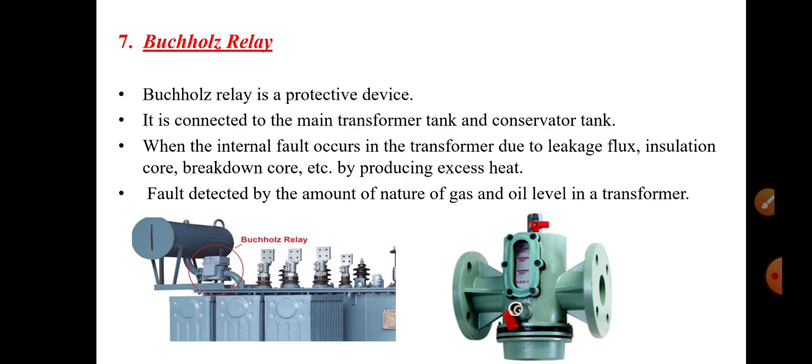The Buchholz relay is a protective device. When internal faults occur in the transformer — because of leakage flux, insulation failure, or breakdown of the core — excessive heat is produced. This heat decomposes the oil in the transformer and gas bubbles are formed. As the gas bubbles flow in the upward direction, they are collected in this relay. The relay detects faults by the nature of the gas and the oil level in the transformer.